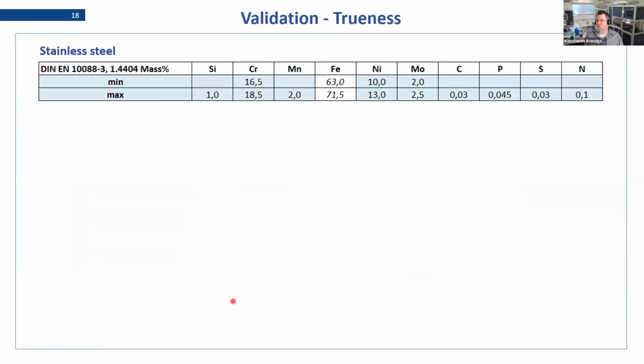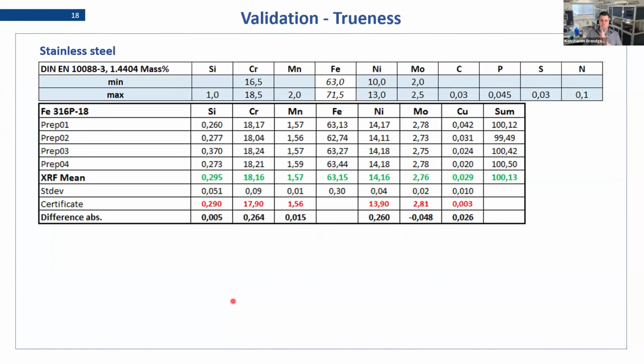And to sum this up then, as a validation for these results, we use these validation samples to look at how correct our results are. Again, there are red numbers here, but don't be confused. Green and red always stick out, so red doesn't mean bad here. Red is the certificate value that we have from the documentation, and green is what we get from our repeated preparations here. And you can see that it matches quite well. So the validation was quite successful.